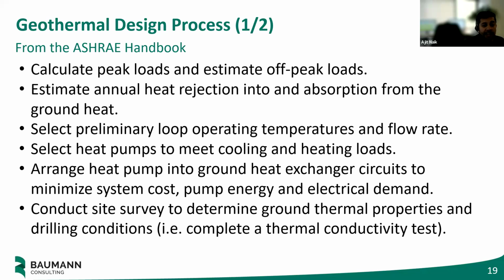Since these systems act as a thermal battery, storing heat underground in the summer and pulling it back out in the winter, it's not like designing a normal system. Those of you who are engineers and have designed a home air conditioning system, furnace, or even a more complex system like a boiler and chiller, typically size those just for the peak, like on the coldest day of the year, how much heat do we need? Same thing in summer when it's July, everything's packed and running, and it's super hot out, what's our cooling load? That's typically how you size HVAC equipment.